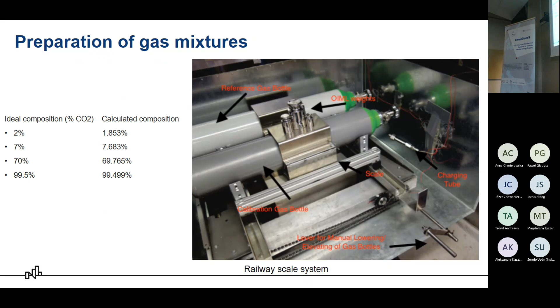And after that, via charging tube, we add CO2. And for GC calibration, it is really important to have a uniform mixture. So a specially designed rolling heating system is used. Here is the calibration gas bottle. The rollers start, they are rolling. And we have to put the lid on it, and we heat it. This is the heating plate.